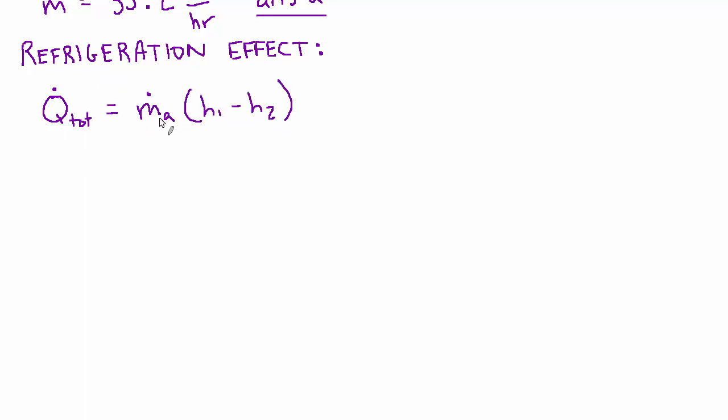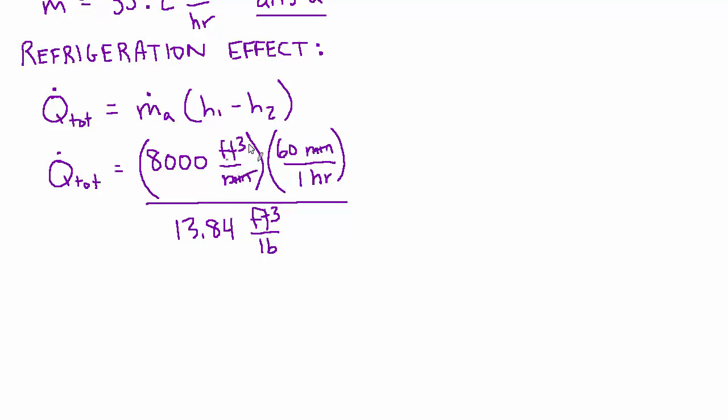And the mass flow rate of air term is going to look very similar. It's the exact same term as we had above. Let's show it all again for completeness. So that's 8,000 cubic feet per minute times the 60 minutes per hour divided by the specific volume 13.84 cubic feet per pound. And we lose minutes and we lose cubic feet. And then we're multiplying by the difference of those two enthalpies that we looked up before. H1 was 31.18 BTU per pound, and H2 is 24.43.